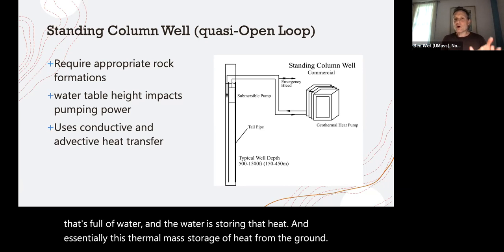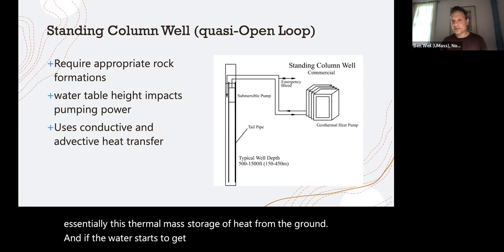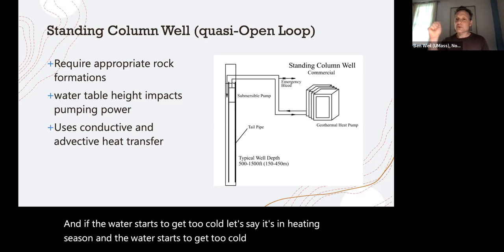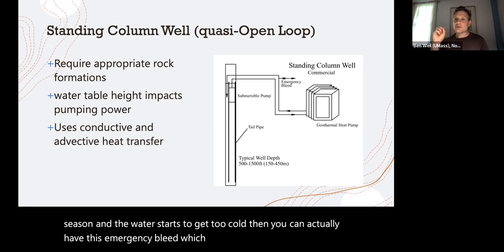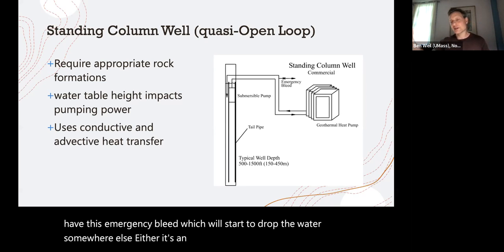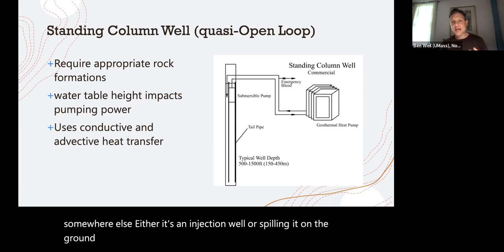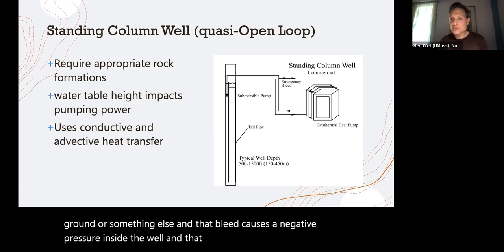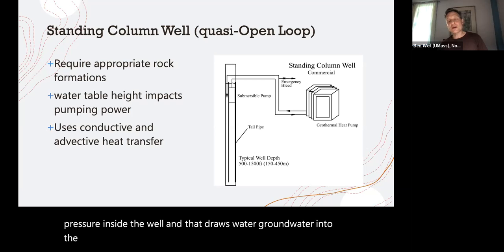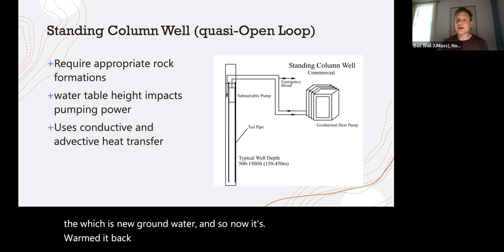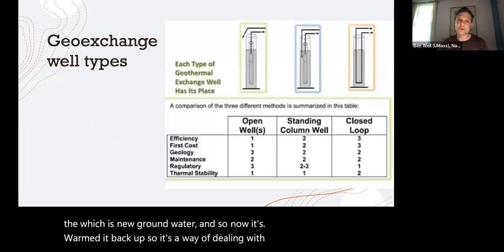And if the water starts to get too cold, let's say it's in heating season and the water starts to get too cold, then you can actually have this emergency bleed, which will start to drop the water somewhere else. Either it's an injection well or spilling it on the ground or something else. And that bleed causes a negative pressure inside the well, and that draws groundwater into the well, which is new groundwater. And so now it's warmed it back up. So it's a way of dealing with an imbalanced system.